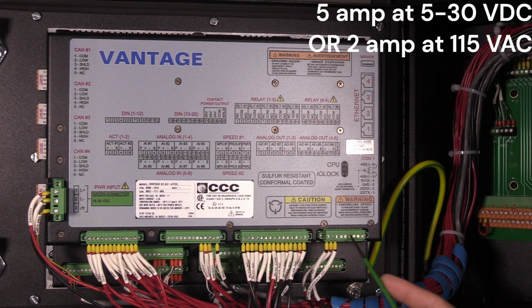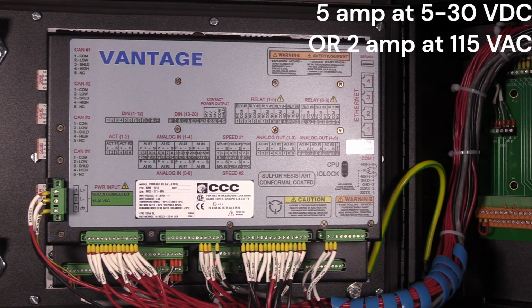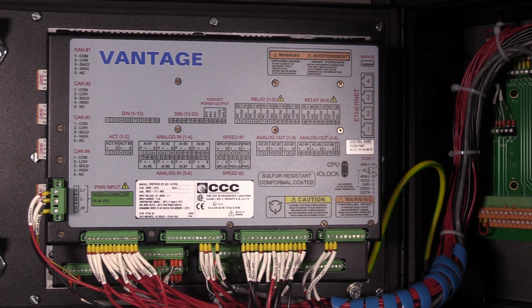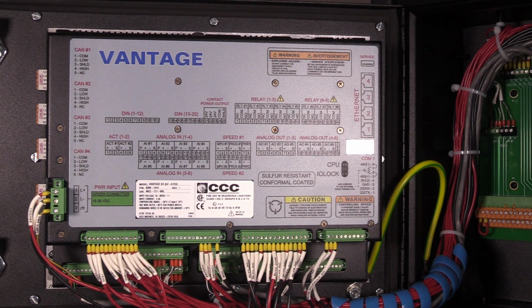The relay contacts are rated for 5 amperes at 5 to 30 volts DC or 2 amperes at 115 volts AC. Before installation, verify that the Vantage's relay contacts meet the power requirements of the circuit with which it is being interfaced. In cases where the interface circuit demands relay contacts with higher power rating, an interposing relay is required.